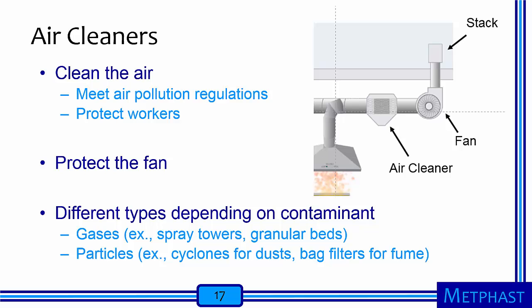Air cleaners serve to clean the air. How well they clean the air depends on the purpose — if the air is being exhausted outside, they need to meet air pollution regulations. Alternatively, they need to be effective enough to protect workers if the air is recirculated back into the facility. Air cleaners also serve to protect the fan, as some gases are highly corrosive and some particles can erode the fan blades. There are many different types of air cleaners depending on the contaminant being cleaned. Spray towers are used to absorb gases, granular beds can also be used to absorb gases, and cyclones and bag filters are common air cleaners for particles.